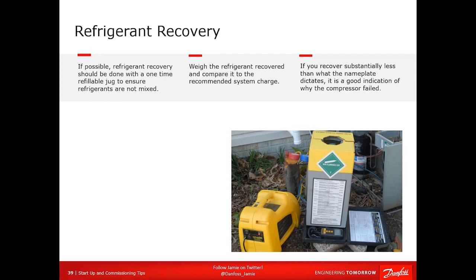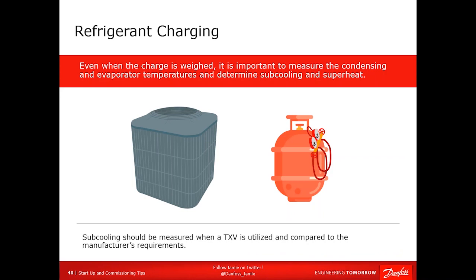Okay, charging. Everybody loves to charge the system, whether it needs to or not. Well, before you charge the system, in fact, before you even pull the compressor out or do whatever, you need to get the refrigerant out of there. Weigh the refrigerant when you remove it. Why? Because you want to know how much was in there. If it's supposed to have 30 ounces and you pull 16, there's a good reason why that compressor probably failed. You need to find out where that refrigerant went.